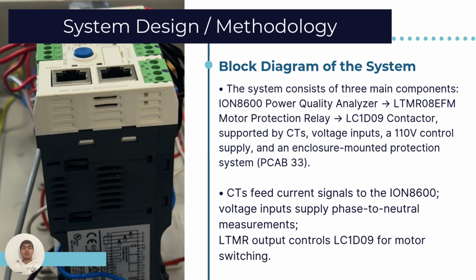And now, system design and methodology. Here is the block diagram of the system. The system consists of three main components: the power analyzer, which is the ION 8600, the LTMR08EFM, which is the relay, and the LC1D09, which is the contactor.